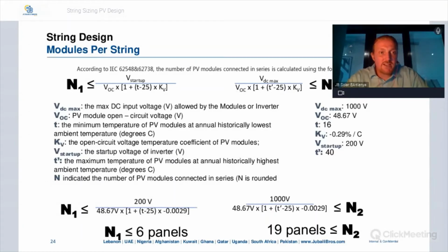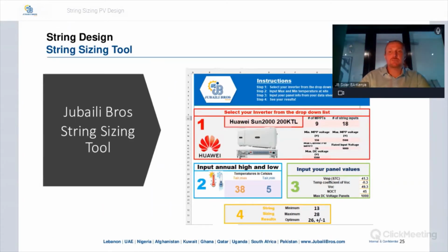You have to take into account all of these variables: the VDC max, the VOC, the open circuit voltage temperature coefficient, the V startup of the inverter, the maximum and the minimum temperature of the PV modules at the annual historically highest ambient temperature. So it's a complicated formula.